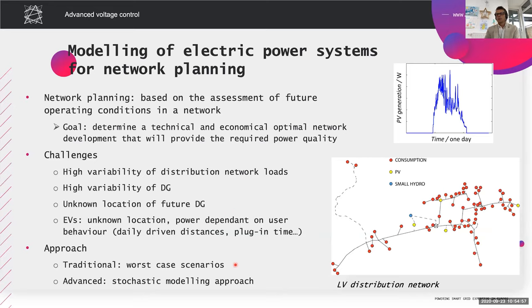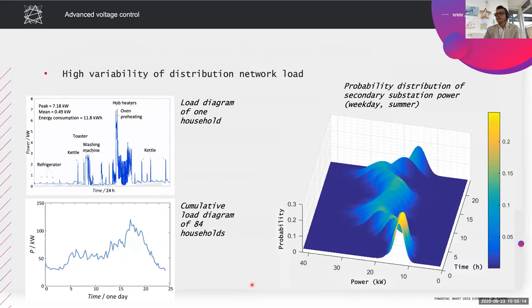Well, the traditional approach would be to assume the worst case scenarios, and this will result in a very expensive network. The more advanced approach is to use stochastic modeling. Let me briefly explain this. In the stochastic modeling approach, you evaluate every distributed generator, load, heat pump, or electric vehicle with some probability curves. This case just shows the probability curves for power distribution on a secondary substation transformer.